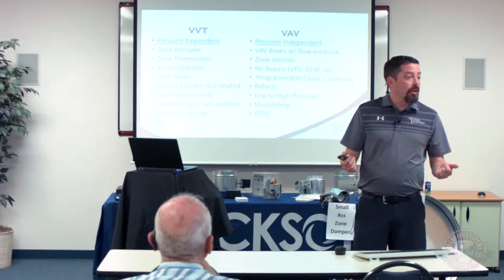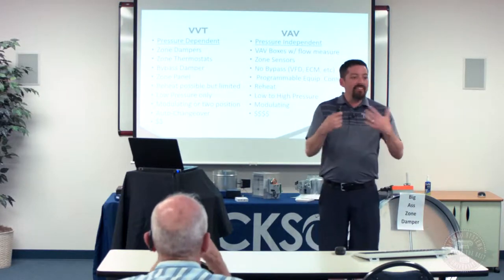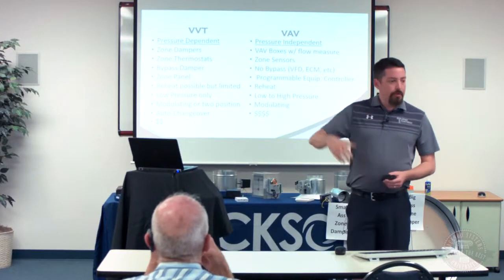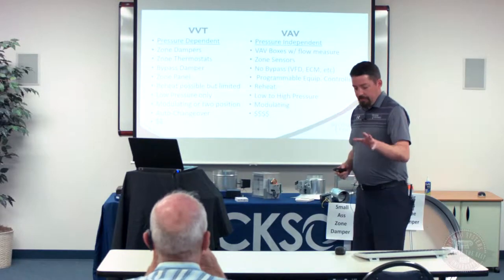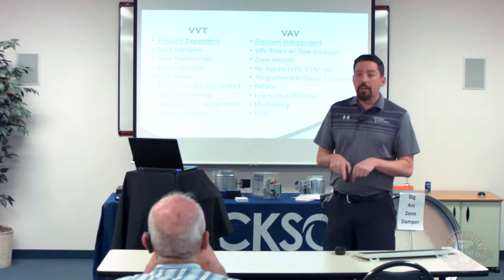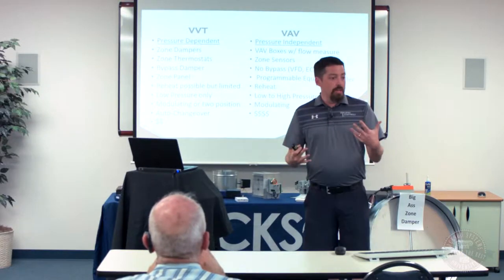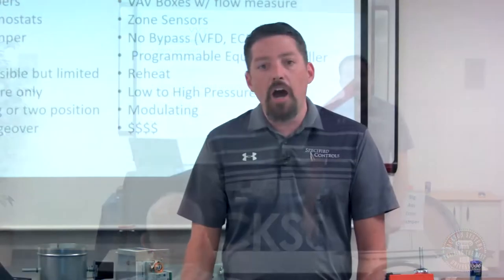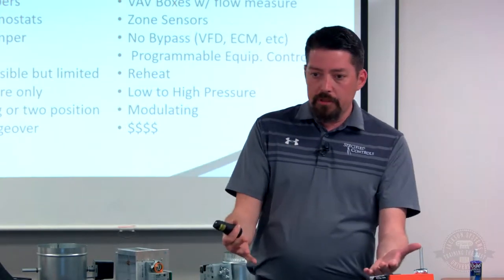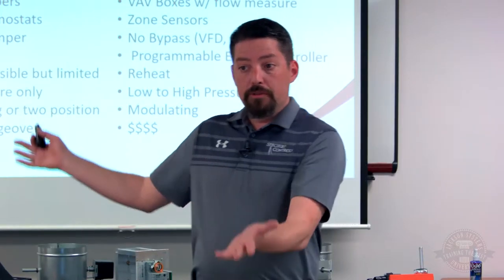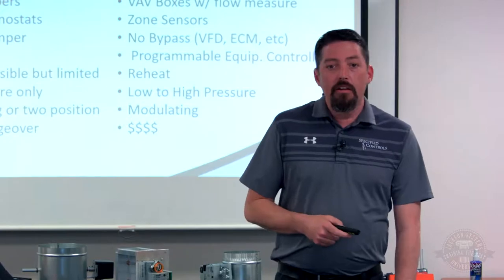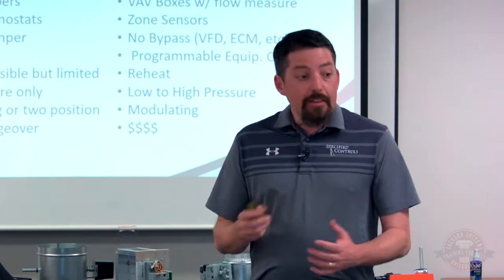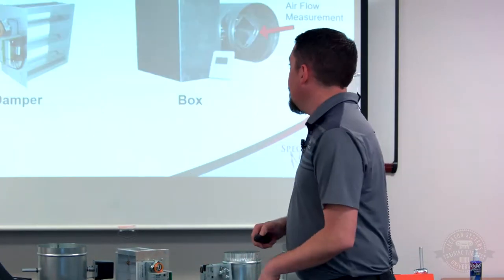Most systems we'll come across are low pressure, but in cities like Chicago or New York you might have three or more inches of static. The VVT concept can be two-position or modulating — open/closed or modulated — and it's always auto changeover, meaning the unit provides both heating and cooling. VVT is going to be much cheaper than VAV — typically half the price or less.